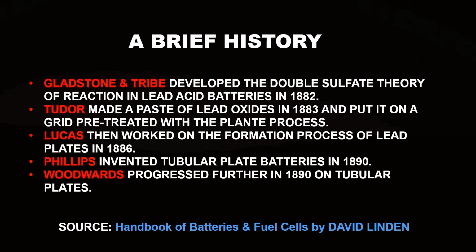Until now, these were all pasted plates where both positives and negatives were pasted. However, when you cycle such batteries having pasted plates, we realize that the positive active material sheds off. Hence, in 1890, Phillips invented tubular plate batteries. This was done to extend the battery's life. Woodward in the same year 1890 further processed these and worked to improve the tubular plates.